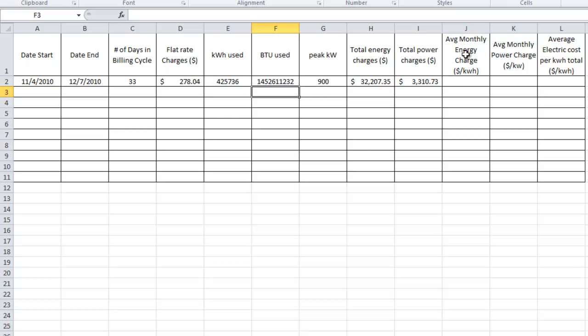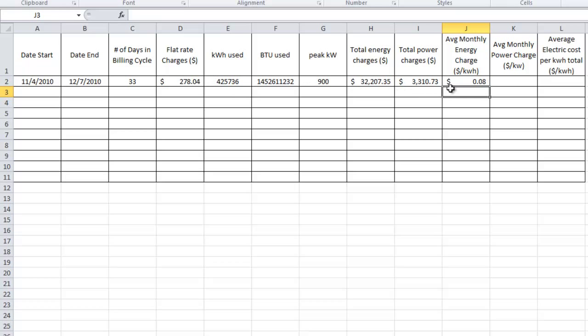Now, the average monthly energy charge — we're just going to take the energy charges in dollars and divide by the total kilowatt hours. So it's energy charges divided by kilowatt hours. This should be somewhere in the order of 1 to 20 cents, and it's going to be different for different buildings. If you get anything outside that range, you've made a calculation error or something from your bill is wrong.